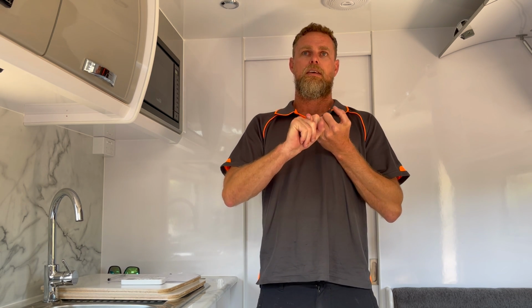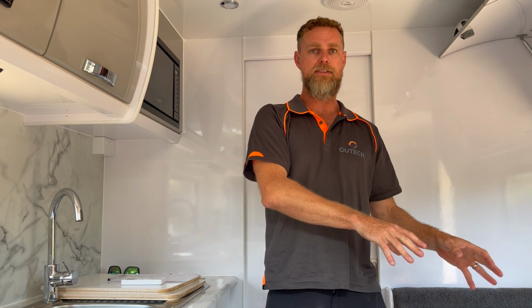There are some manufacturers out there promoting their battery as being able to be connected to any charger without issue. They can't do that anymore, because you now need to have a battery monitor. In accordance with the standard, the battery monitor needs to be able to monitor voltage and state of charge. If you have an AGM battery system and you change that over to lithium but leave your chargers as AGM chargers, you do not have a compliant system, because you don't have a battery monitor in that system that is compliant to that lithium battery.